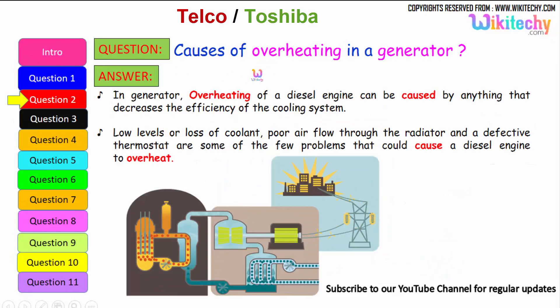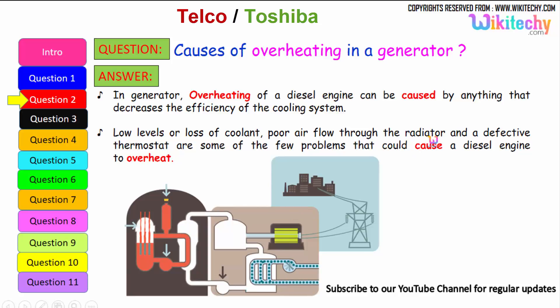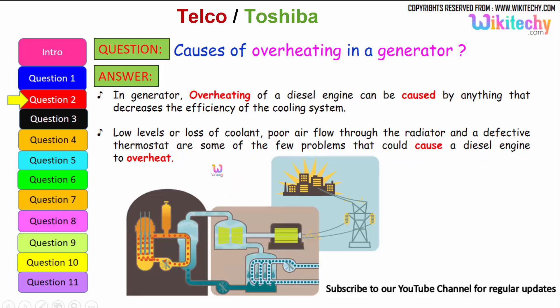Let us move on to the next question: causes of overheating in a generator. Overheating of a diesel engine can be caused by anything that decreases the efficiency of the cooling system. It can be due to the loss of coolant or low levels of coolant, poor airflow through the radiators, and a defective thermostat — some of the few problems that could cause a diesel engine or a generator to overheat.